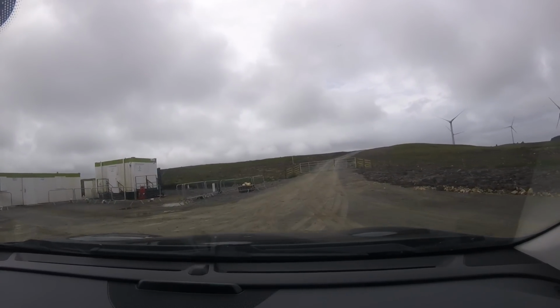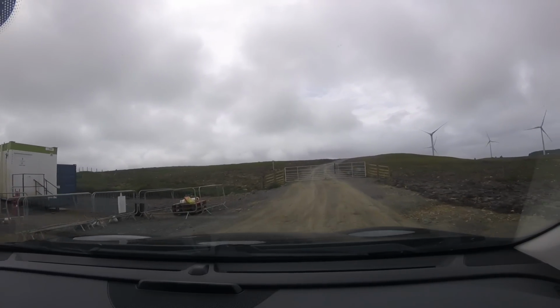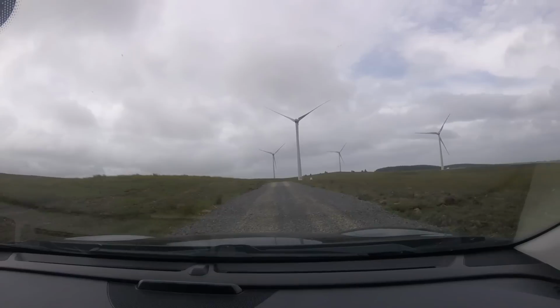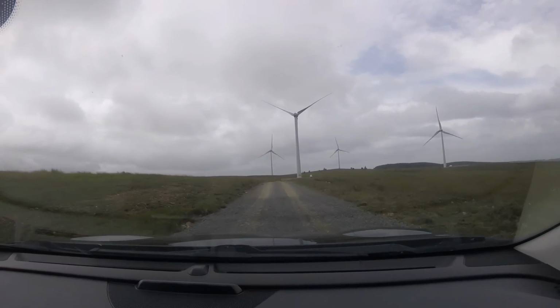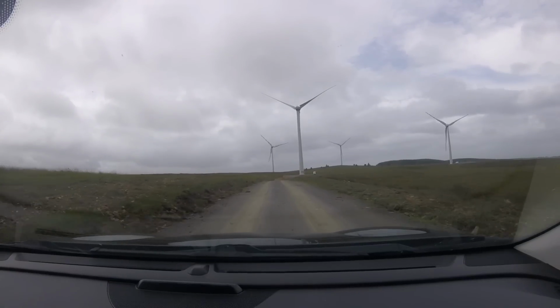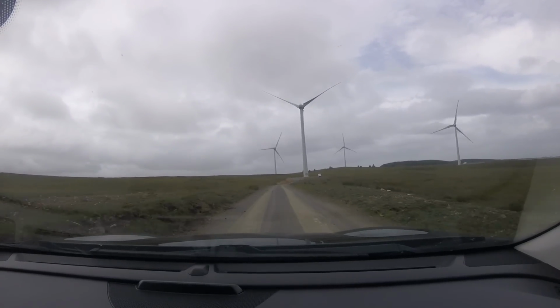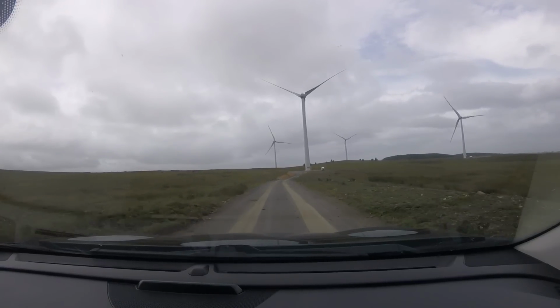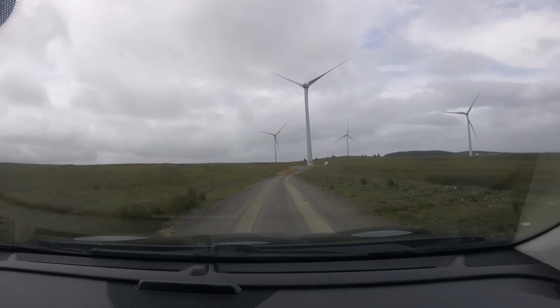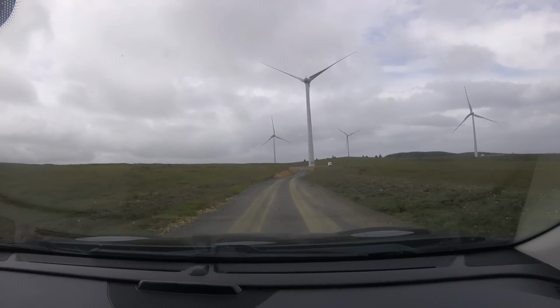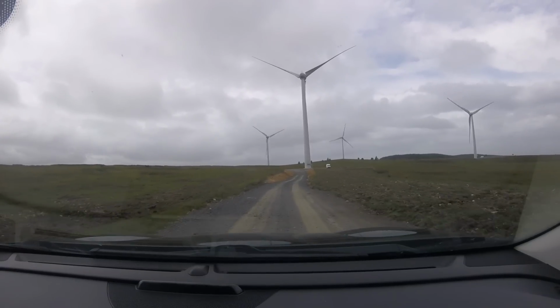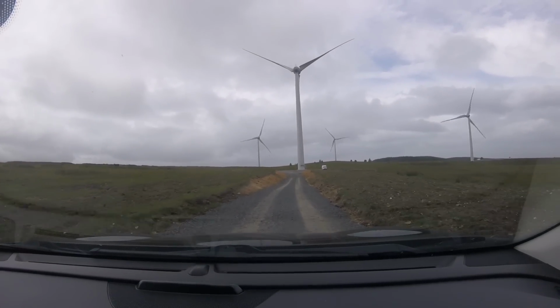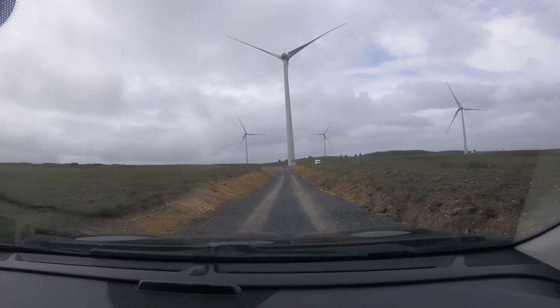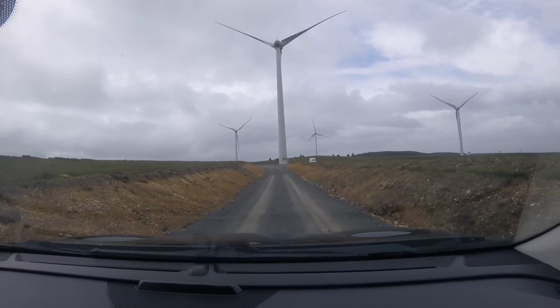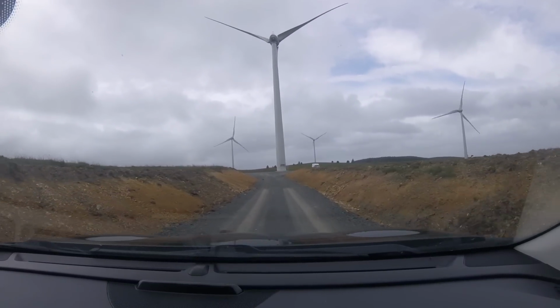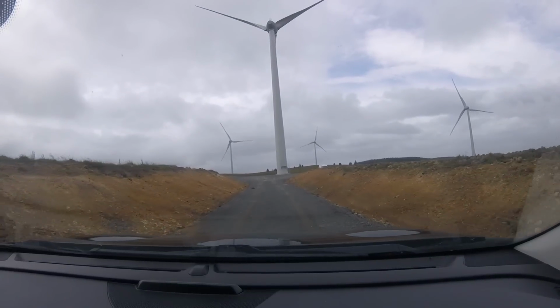So as I say, we'll head up this road here, which is Road 1 mentioned before. The 300-hour maintenance, as the name suggests, is what gets completed in the turbines after their first 300 hours of run time. It's a one-off type of servicing, only happening at this point in the turbine's lifespan, and they check quite a number of things, but primarily it's a matter of checking the torque of the bolts in the towers to ensure that nothing has loosened off during the first period.